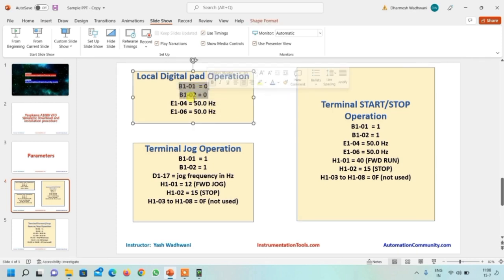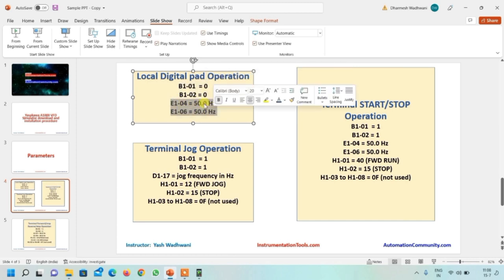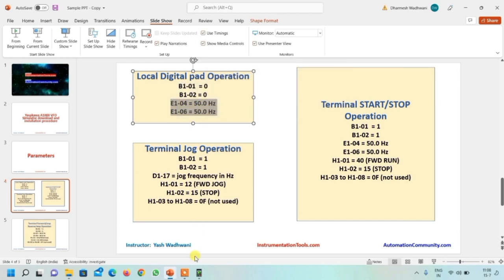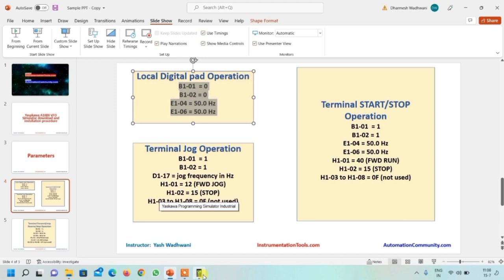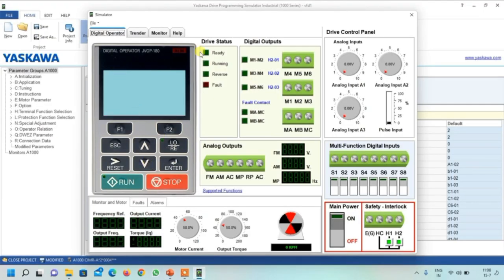These two parameters enable the keypad, and these two parameters are for setting the frequency. By default it is set to 60 Hz, but we use 50 Hz in India, so we need to change the frequency accordingly. By writing just these four parameters, we will be able to do simulation by keypad.